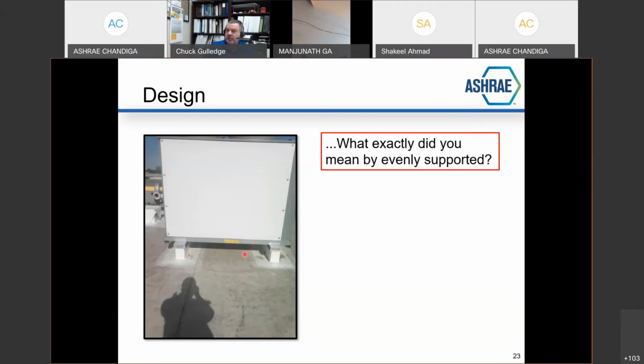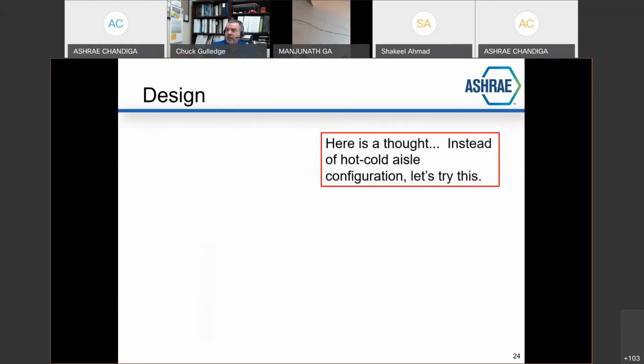Somebody looked at static drawings. The way the drawings got plotted, there was like a break line in the drawings right here. That base was on one drawing. This base was on another drawing. Somebody measured those drawings wrong and set one of these in the wrong location, and nobody checked it. And nobody checked this when it was on the ground to make sure that center line spacing was going to work. They put it on the roof knowing it was problematic, and they walked away, and I go up there. That's my shadow. I go up there and find this was left. That's just horrible.